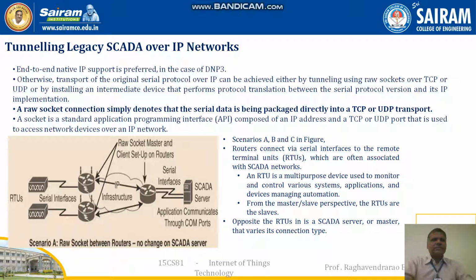The routers connect via a serial interface to the remote terminal units, RTUs, which are often associated with SCADA networks. This RTU is a multi-purpose device used to monitor and control various systems, applications and devices, managing automation. From the master or slave perspective, the RTUs are the slaves. That is, remote terminal units are slaves. Opposite to the RTU in the SCADA server is a master that varies its connection types.